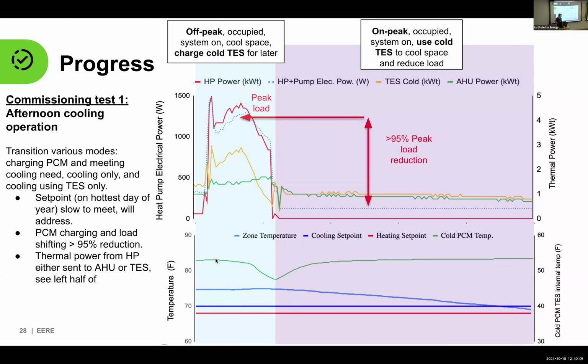You can see in the plots of temperatures that the green line here is the average of 3 temperature sensors inside the phase change material-based thermal battery. The temperature keeps falling and falling, and then you get this precipitous change here, going from around 53°F down to below the freezing point of the material.